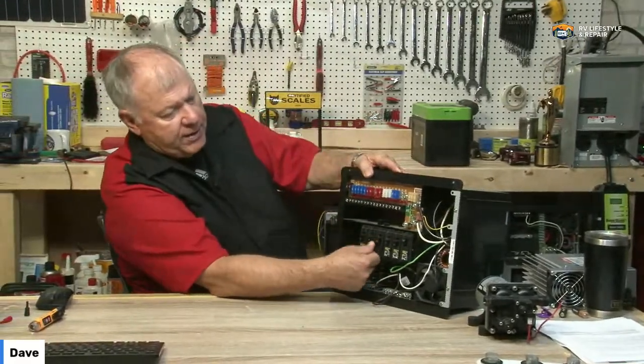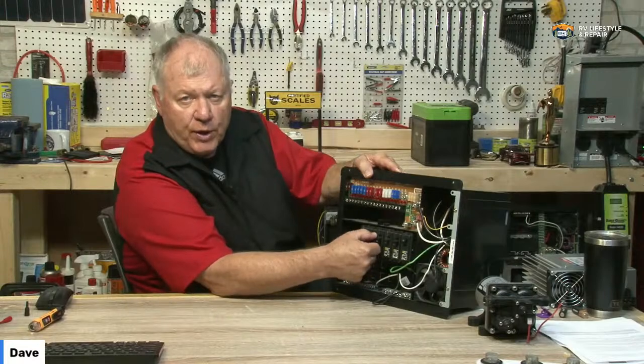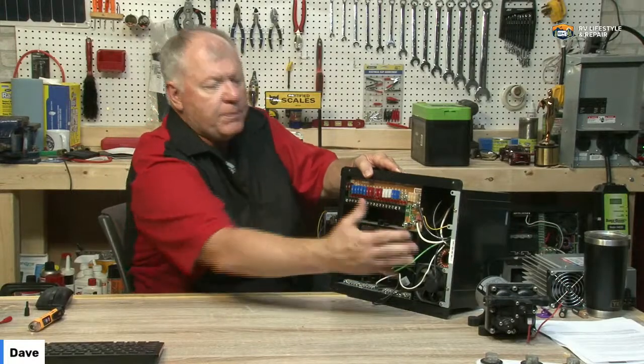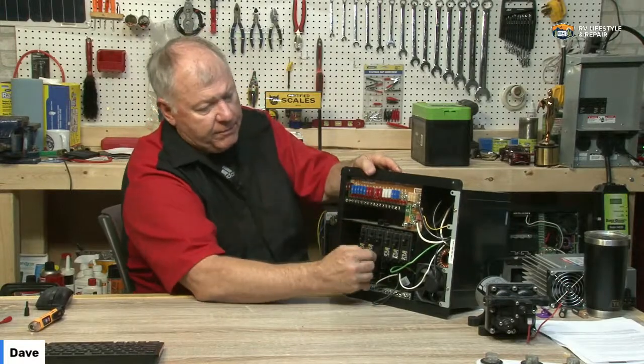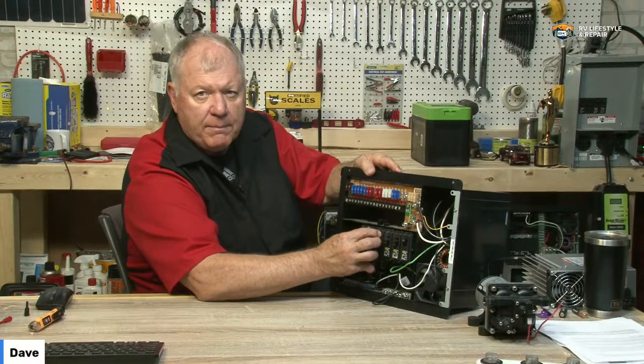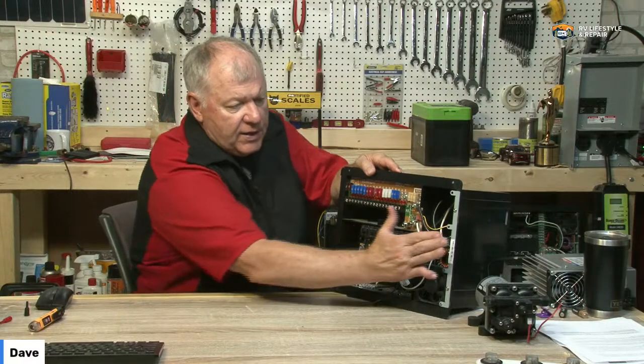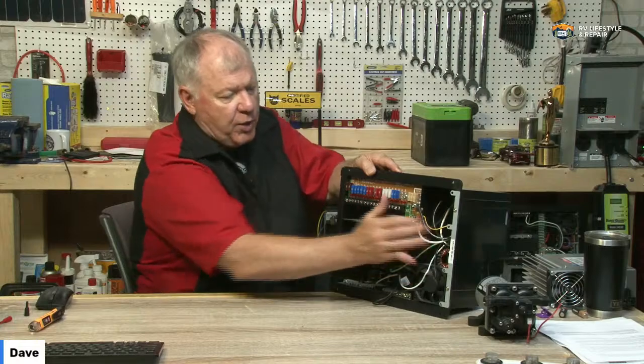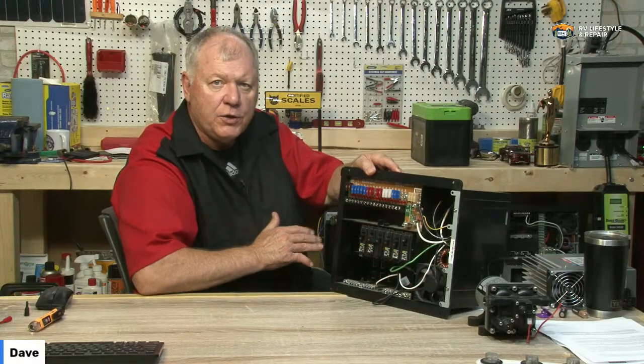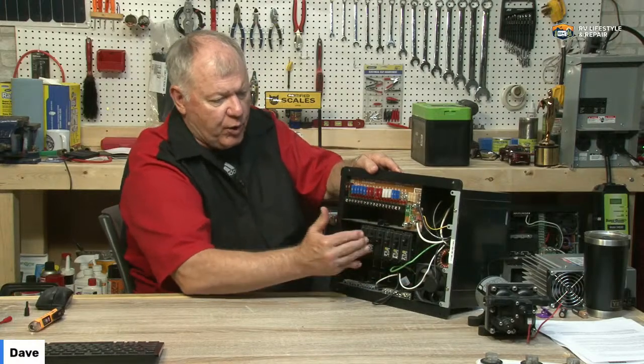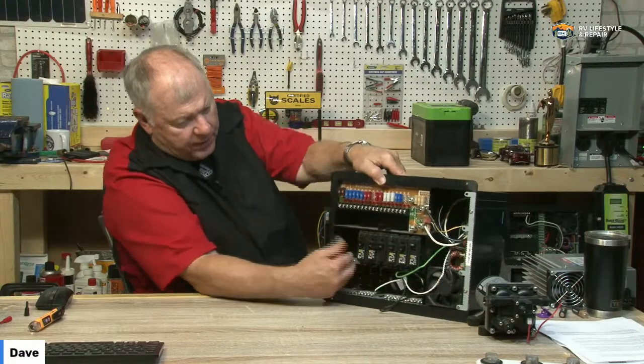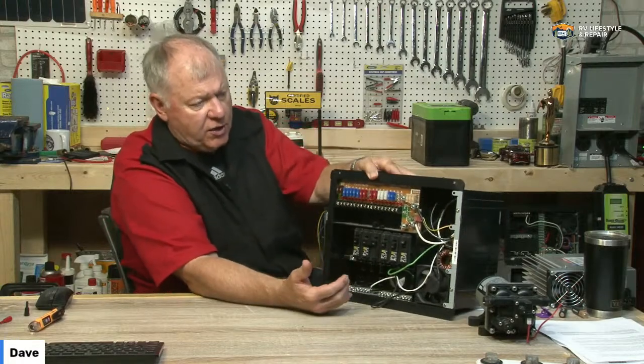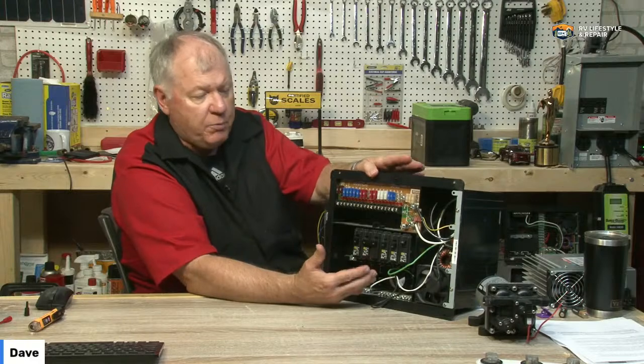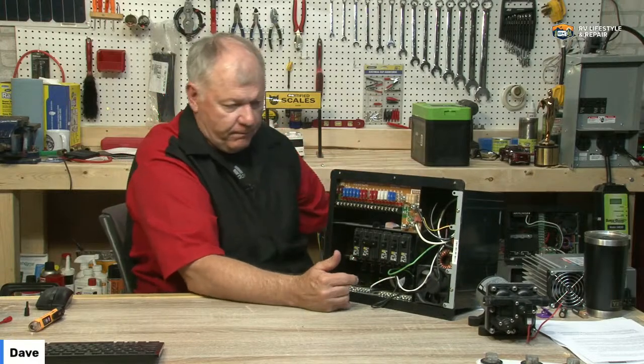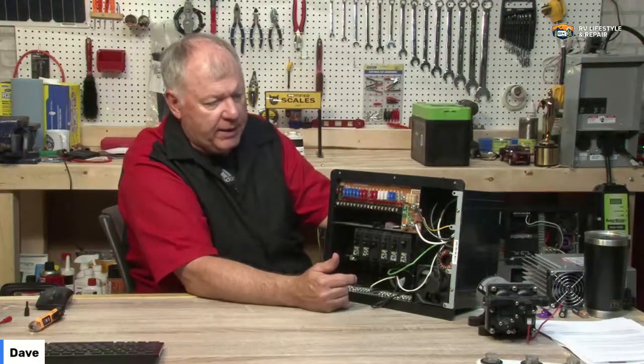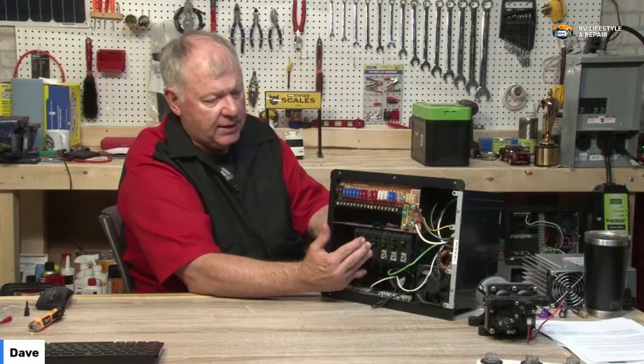So in this one, and yours would be the same thing, you've got 30 amps coming up to your main breaker system, supplying the whole line. In a 50 amp service, you'll have two 50 amp breakers. This half has L1 supplying it, this half has L2. So there has to be a breaker between this bus bar, as it's called, on the bottom. You'll have to swap out the distribution center for a 50 amp one, rewiring it with L1 coming into one side and L2 into the other.